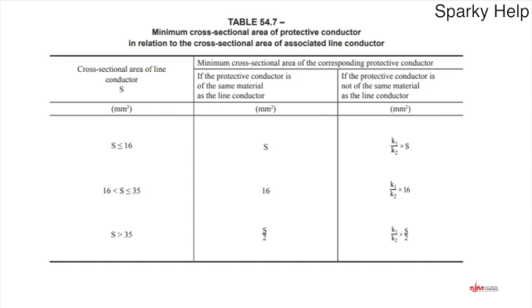It's saying that the CPC, the earth protective conductor that you're going to put in, will be 16. So if you think about the tails you might put into a domestic installation, 100 amp supply, the meter tails are 25 mil. The earthing conductor that you would put in would be 16, and this is what the electricity company would quote you for 100 amp. But if it was a 35 mil, then it would be 16 as well. That's also required. The very bottom one is basically saying cables bigger than 35 mil, and the largest one they make in a copper cable is 1000 mil, and you divide that cable size by 2. So if you had a 50 mil cable, you divide that by 2, that becomes 25, and they make a 25, so a 25 mil earth is what would be required.